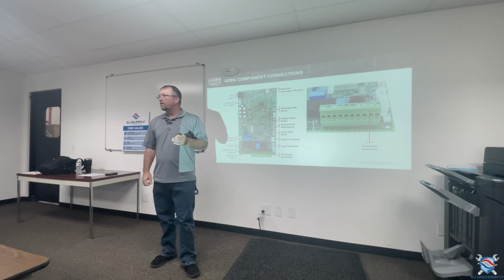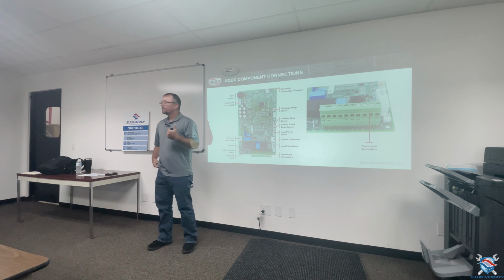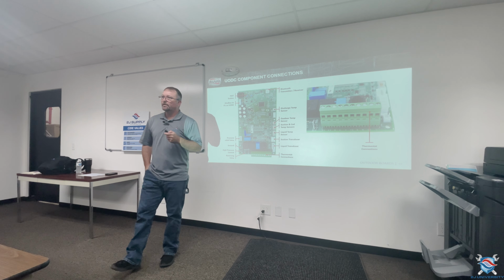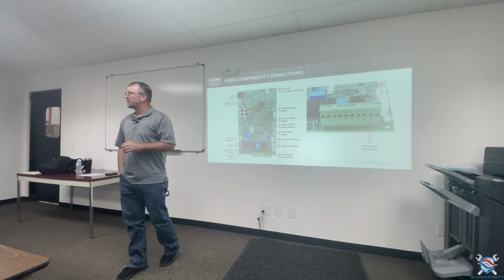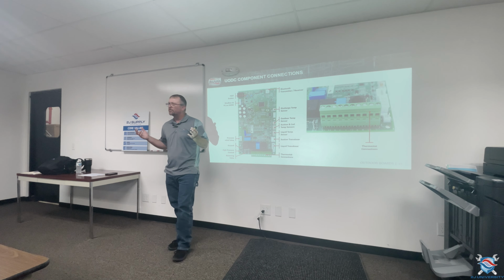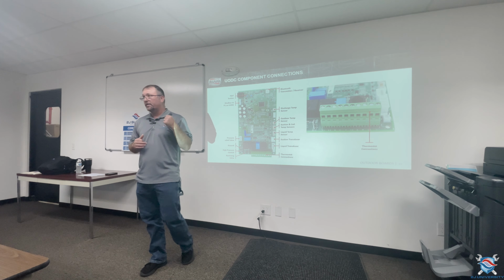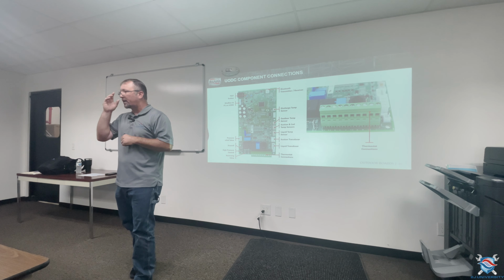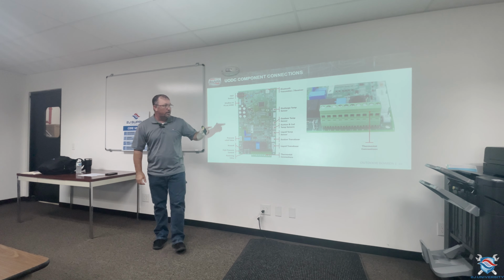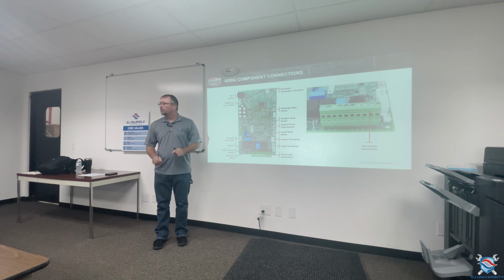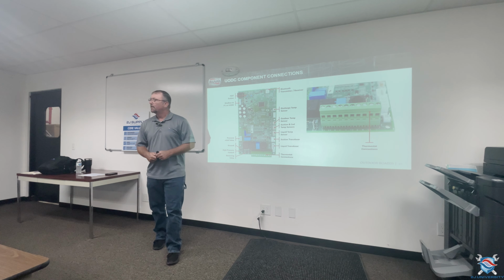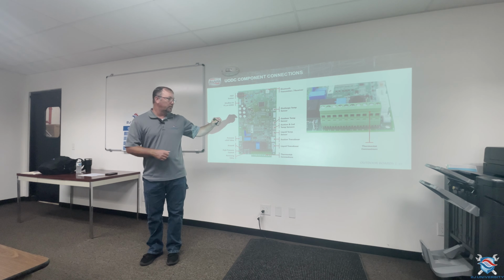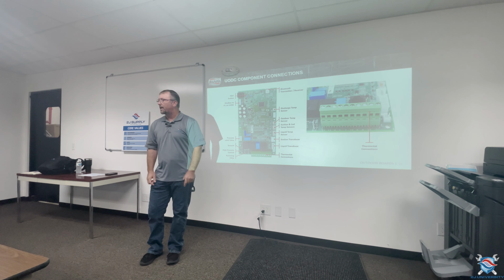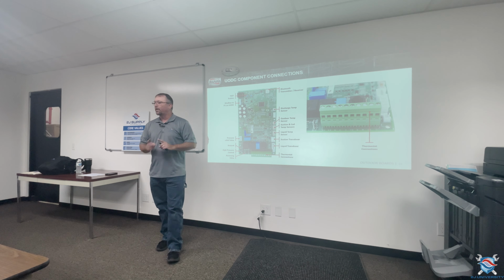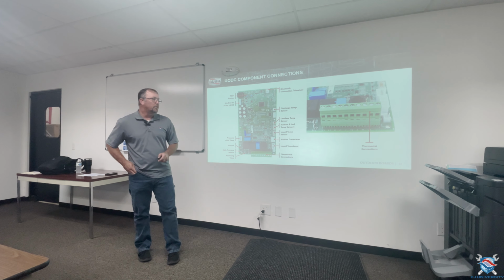U1 and U2, does anybody know what those are for? It's for your utilities when you're using load shed devices. I don't know if you guys have a lot of load shed devices up here. I know in Cincinnati they're all over the place through Duke Energy down there. But that's how you would hook in your load shedding device. You never want to break R or anything like that, because if you do, you're going to interrupt your E1 and E2 every time that R is dropped out of the circuit. So you'll start throwing error codes. So you always want to wire into U1 and U2.